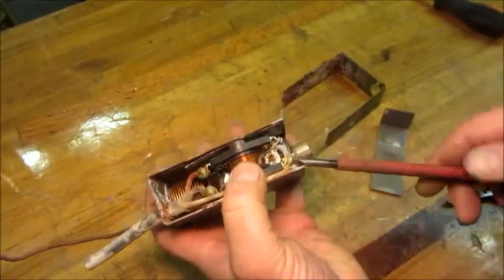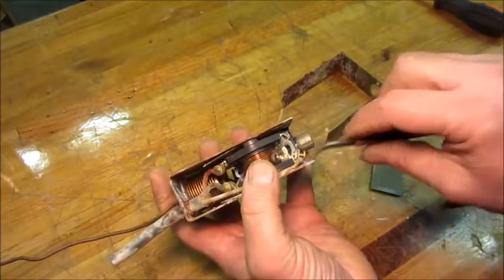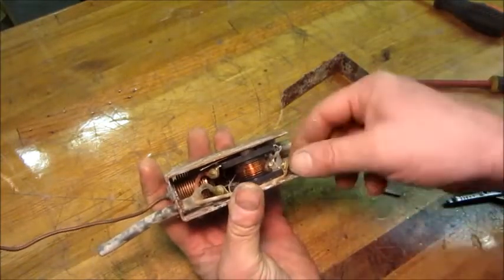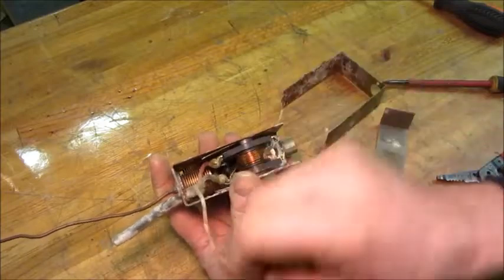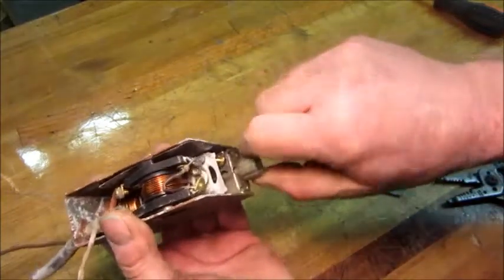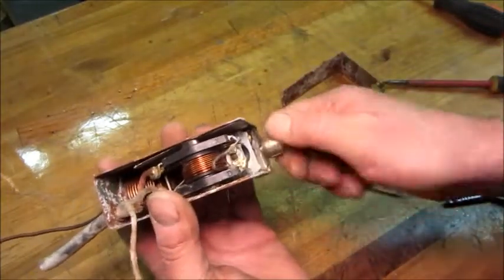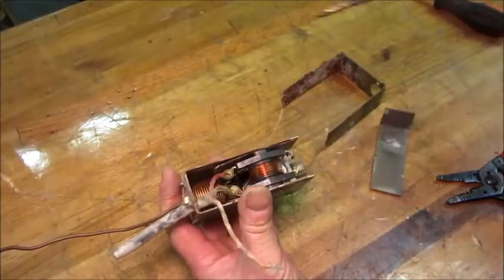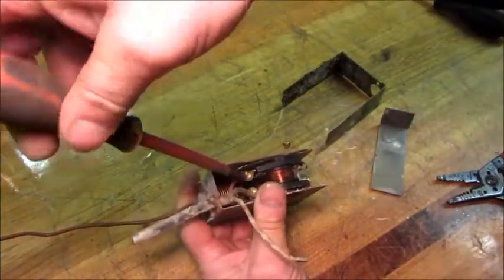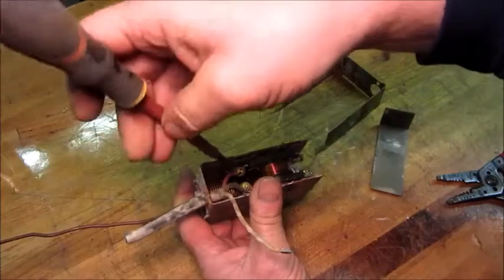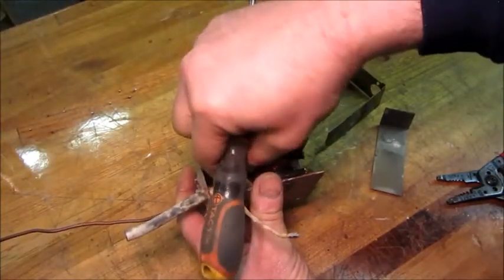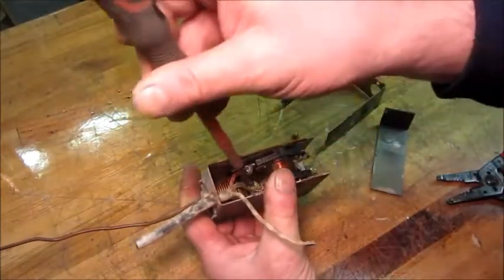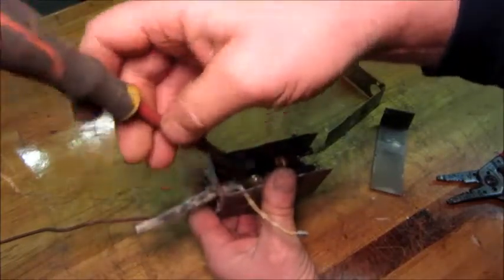As you remember, when I had the compressor running hot wired and it was cold in the evaporator, I could turn the knob down and I could hear the thermostat click on and off, and not right at the beginning where off and on is. I mean, it had to go all the way cold before it would click off. So pretty sure the thermostat itself is working. It's just that we're not getting that pulse of current to the start winding.